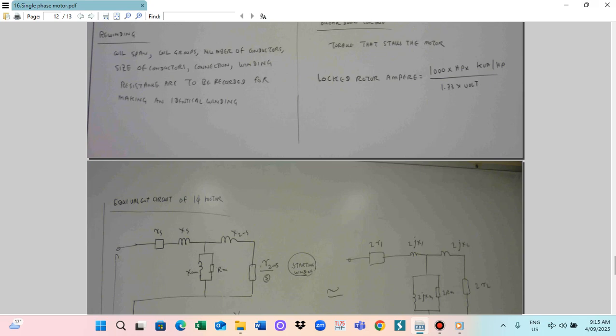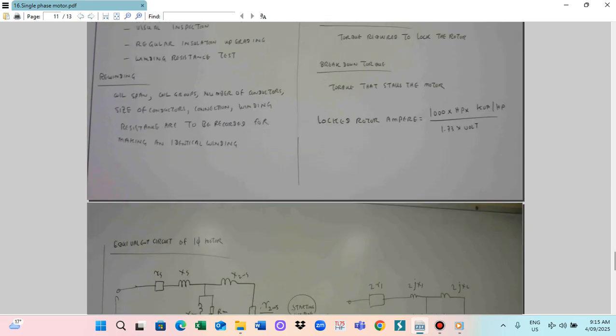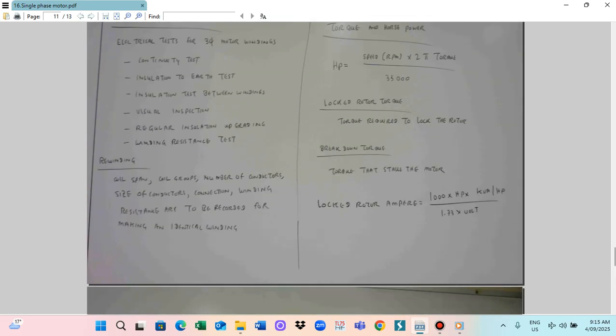In this case, locked rotor kVA per horsepower can also be calculated. When the rotor is locked, you can also calculate the locked rotor ampere: 1,000 multiplied by horsepower, multiplied by the kVA per horsepower, divided by 1.73 multiplied by the volts.